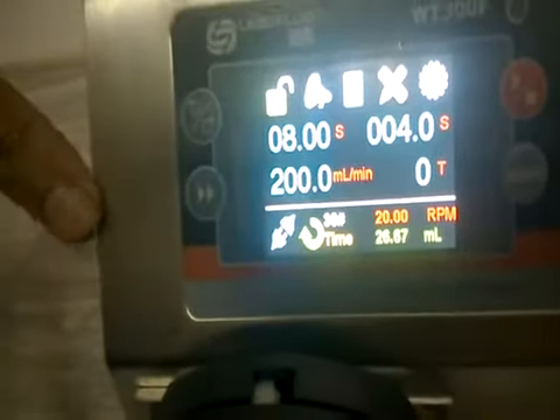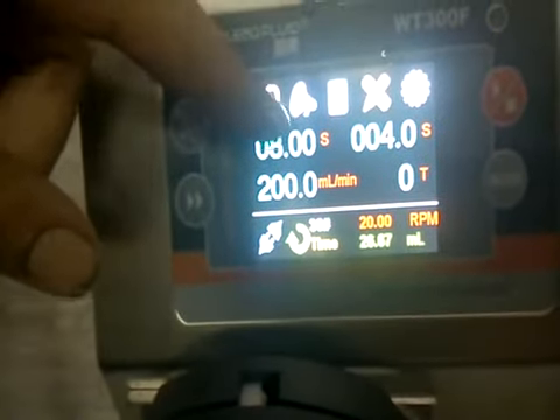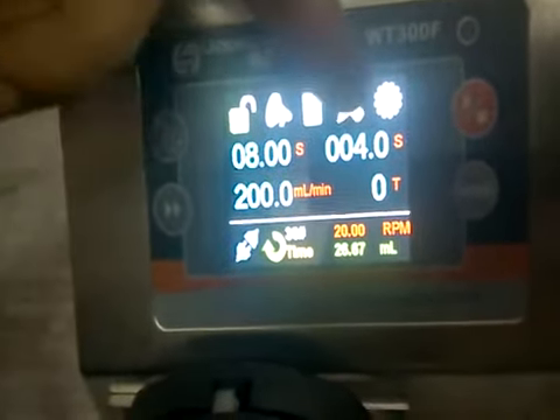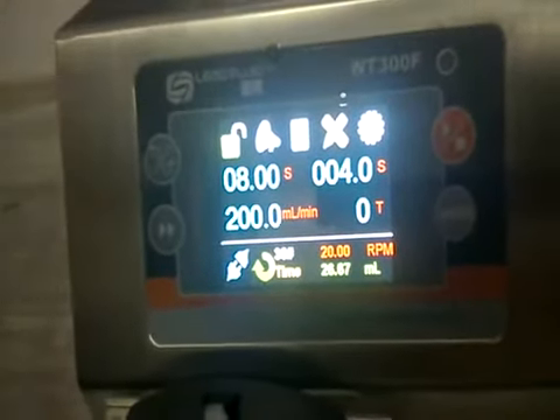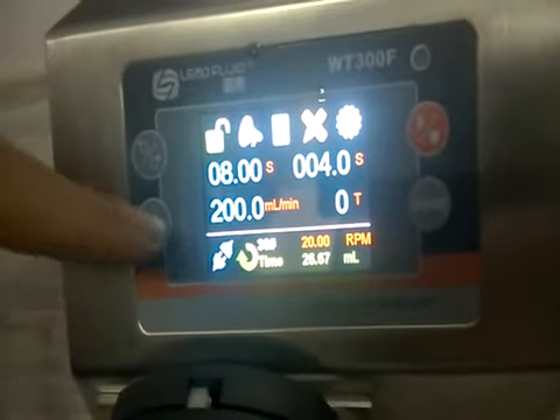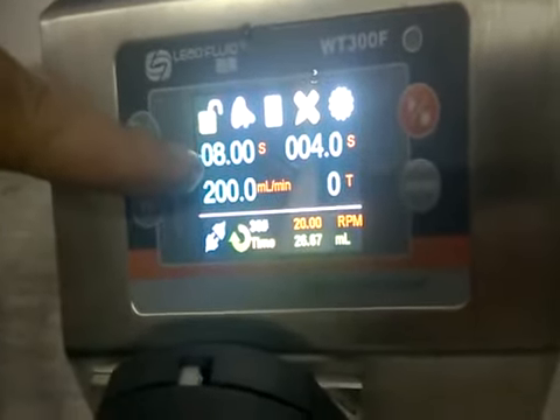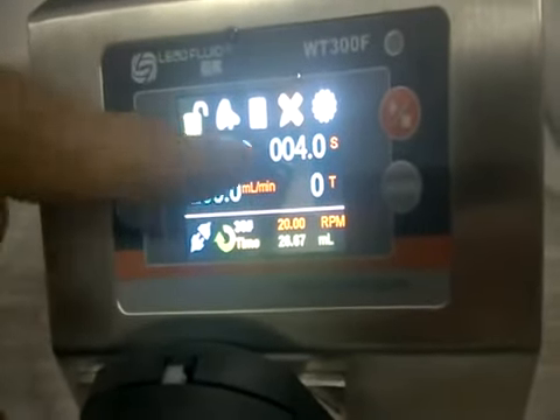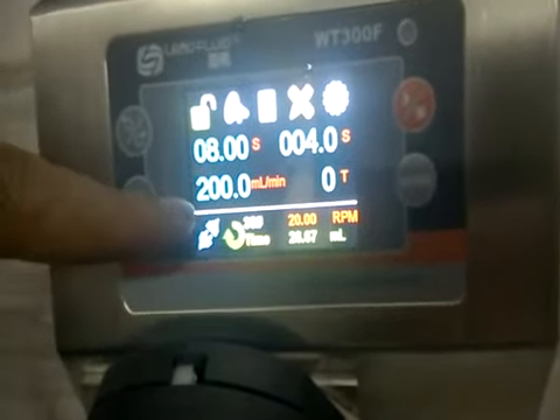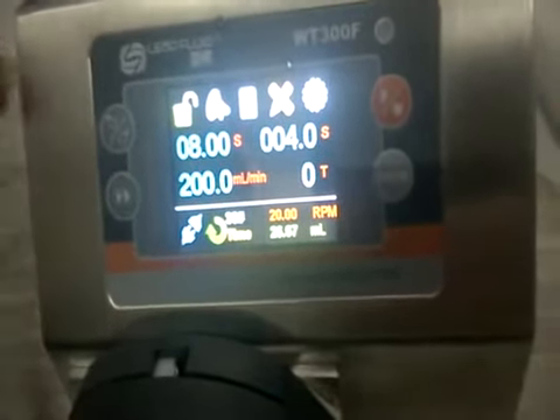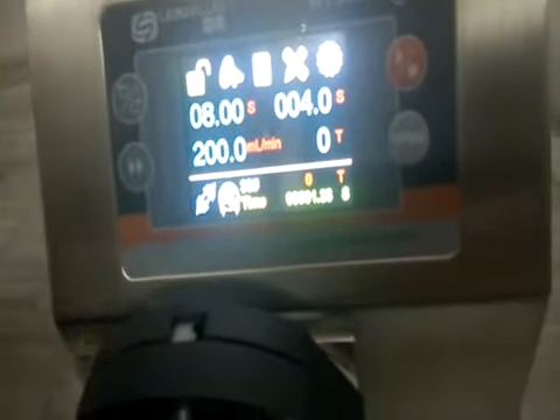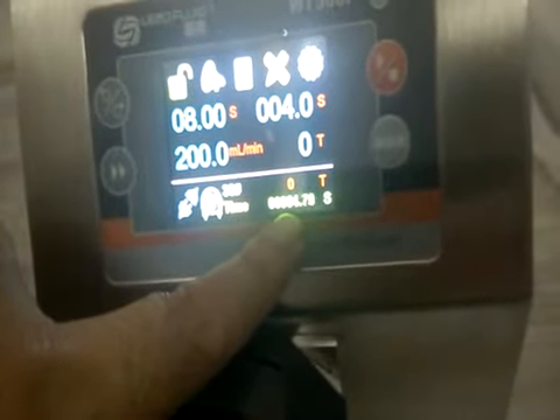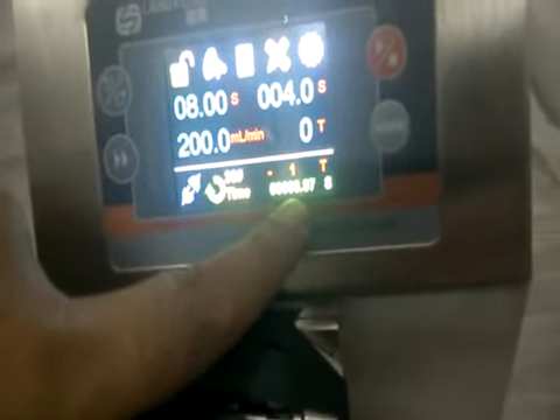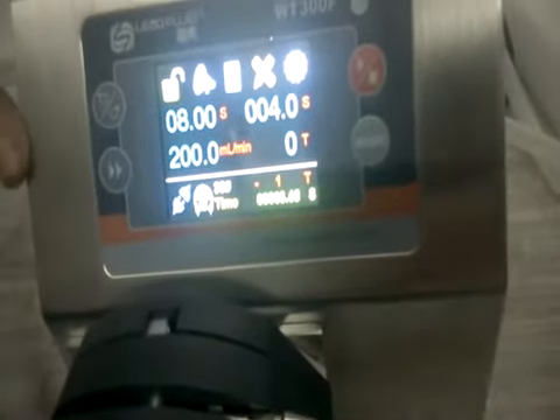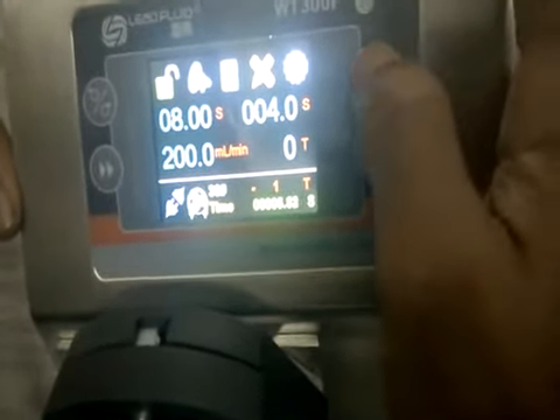The next mode is the time mode. In time mode, you can select your flow and you can select your time for how much time you need this flow, and you can select the interval time also, like 4 seconds. T has to be 0. So what it will do, it will dispense for 8 seconds with a flow of 200 ml per minute, then it will stop for 4 seconds, then again it will dispense for 8 seconds with a flow of 200 ml per minute. Let us see how it does. I am starting it. So for 8 seconds it will dispense with a flow of 200 ml per minute. Now it will stop for 4 seconds, now again for 8 seconds. This will keep on going. These are very good functions.